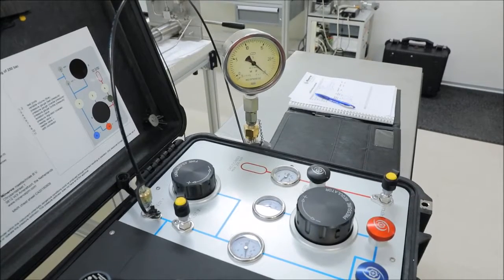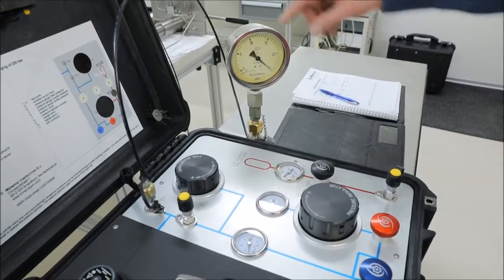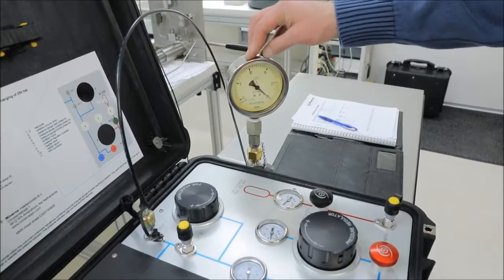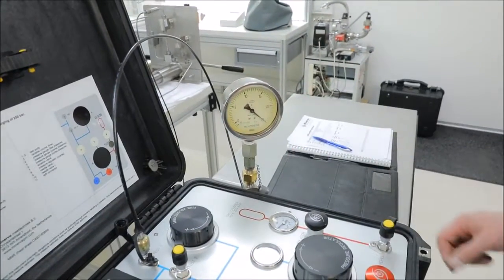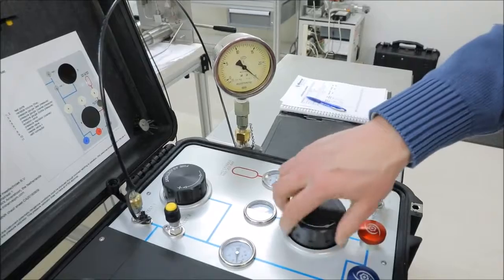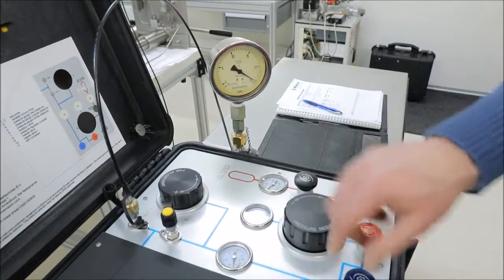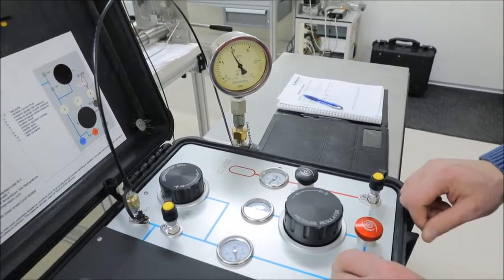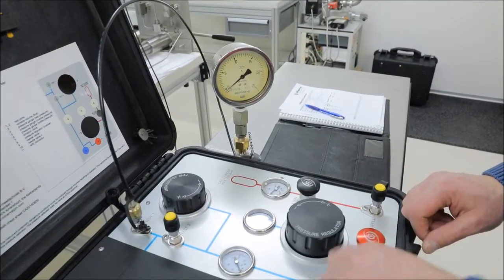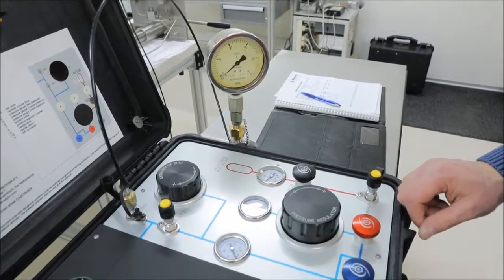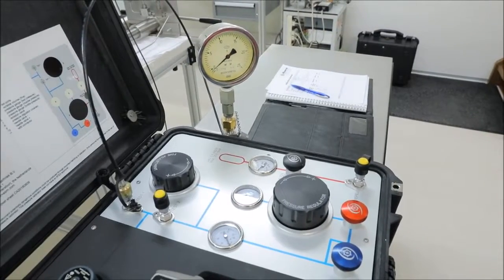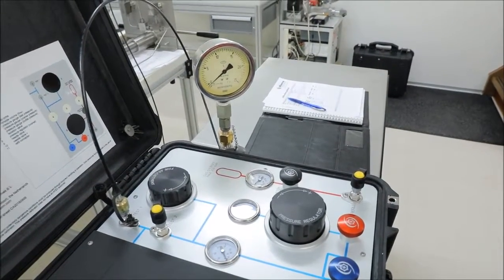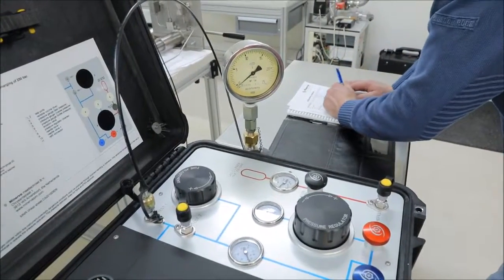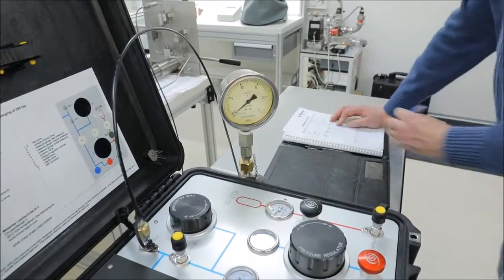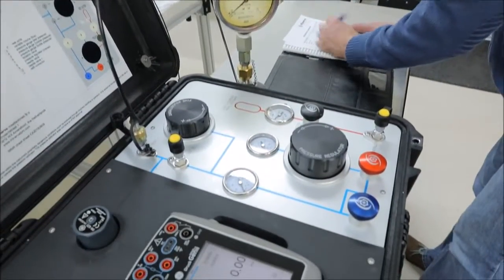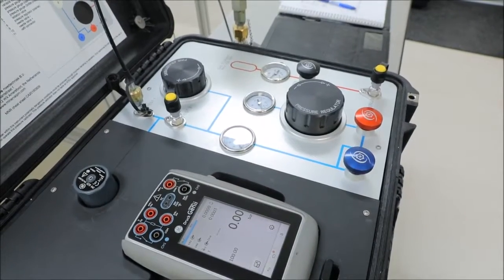So dependent on the procedure, we're going to run a full excursion downwards, or in this case for the demonstration video, I will just send and record the 0. Up valve closed, I manipulate the regulator pressure down, open my vent valve, and the 0 is again minus 0.05, against my reference being 0. So this was the end of the calibration.